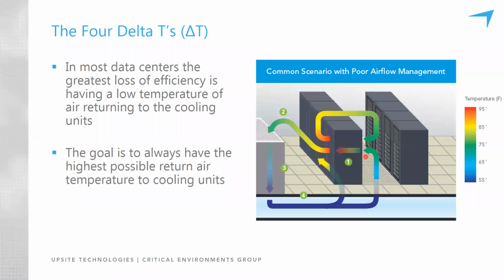Well, obviously, some warm air mixed in from somewhere, indicating a need for improved airflow management. And when the air leaves IT equipment, we all know that it often leaves at 100 degrees or more, but the return air temperature to cooling units is very, very rarely ever near that high. So why does the air cool off from 100 down to say 70? Why does the air drop 30 degrees? Why is there a delta T in that location where there really shouldn't be any delta T?